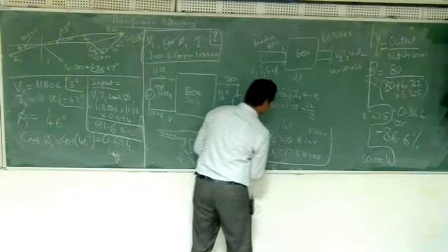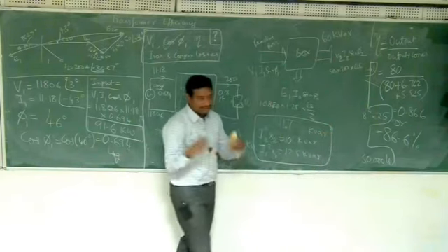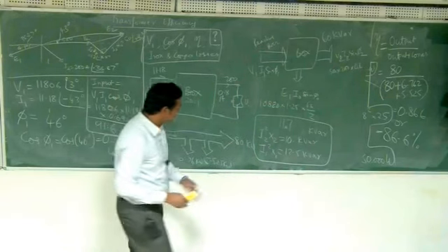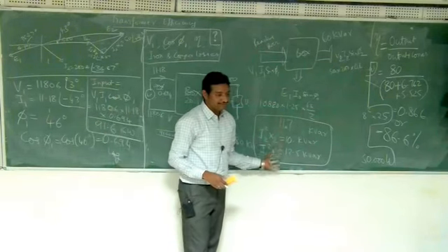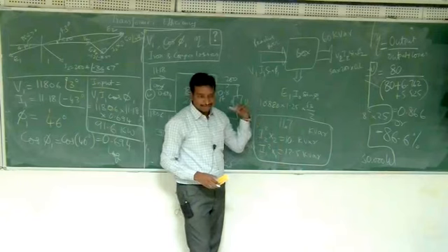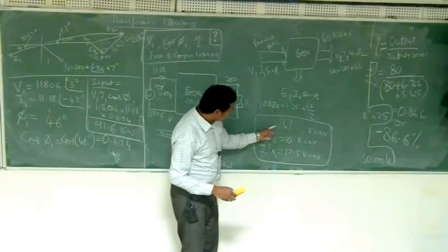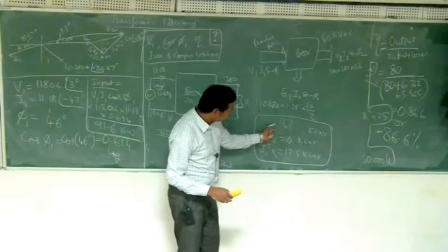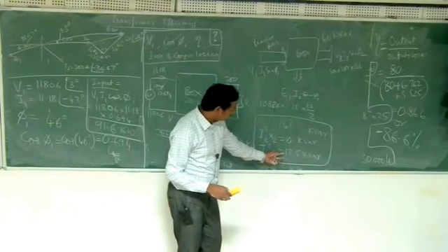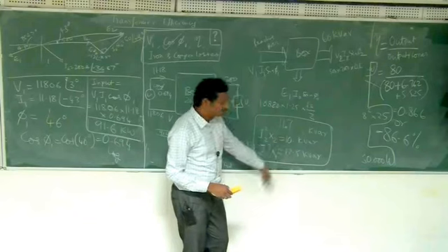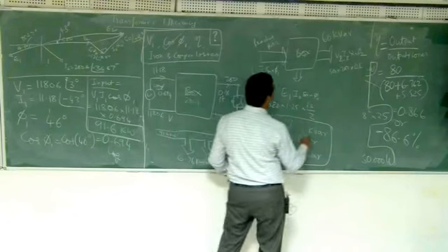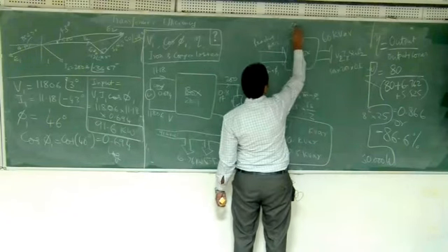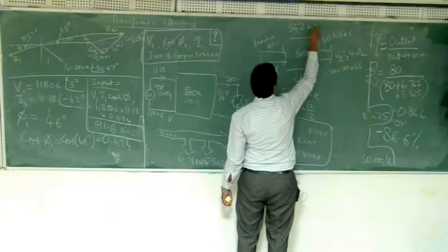So these three are my reactive power losses, where the reactive power is going in the transformer. Who is responsible for giving all this reactive power? The primary side. Let's calculate: 11.7 plus 10 is 21.7, plus 12.5 is 34.2. The total reactive power losses will be 34.2 kVAR.